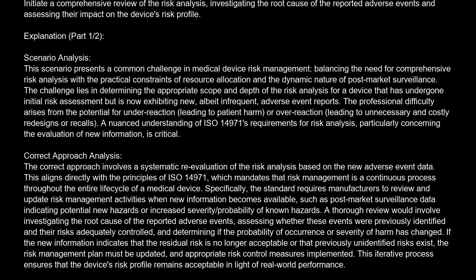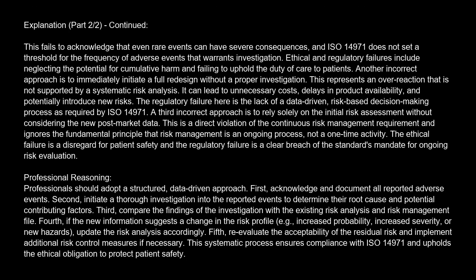Incorrect approaches analysis. One incorrect approach is to dismiss the adverse event reports solely because they are infrequent. This fails to acknowledge that even rare events can have severe consequences, and ISO 14971 does not set a threshold for the frequency of adverse events that warrants investigation. Ethical and regulatory failures include neglecting the potential for cumulative harm and failing to uphold the duty of care to patients. Another incorrect approach is to immediately initiate a full redesign without a proper investigation. This represents an overreaction that is not supported by a systematic risk analysis. It can lead to unnecessary costs, delays in product availability, and potentially introduce new risks. The regulatory failure here is the lack of a data-driven, risk-based decision-making process as required by ISO 14971.